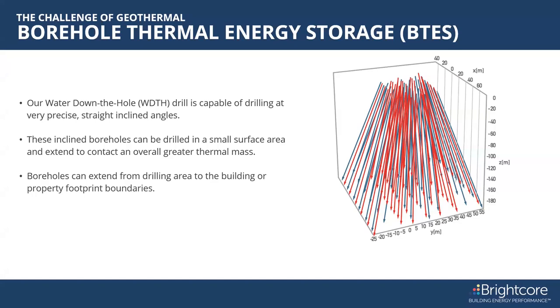What we've done here at this particular site, and as we've even done it in New York, is to use air source heat pumps in combination with ground source heat pumps, so that whoever's winning the efficiency battle at that time takes over. So we can pre-charge the bedrock using air source heat pumps during the shoulder seasons, and therefore in the peak seasons use ground source heat pumps, where the COPs are 4, 5, 6, and air source heat pumps' COPs are 1, 2.